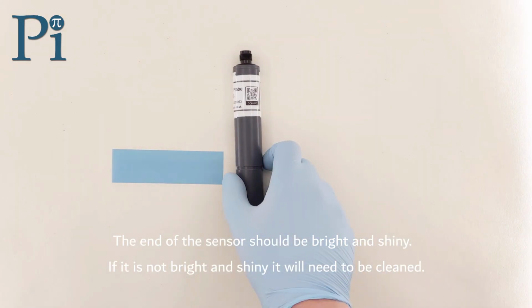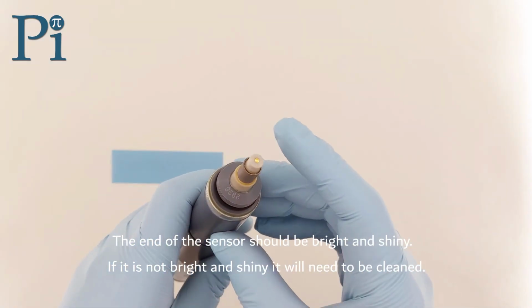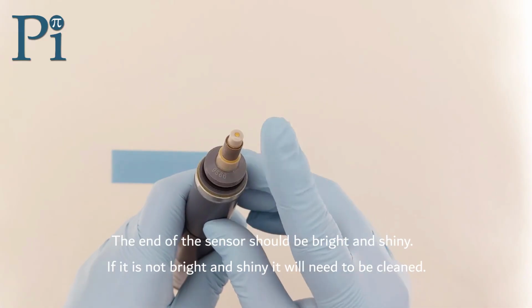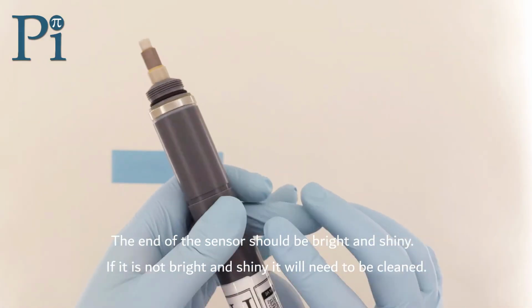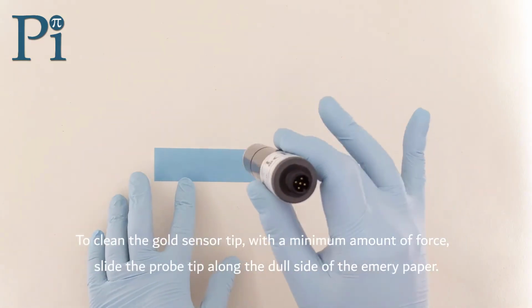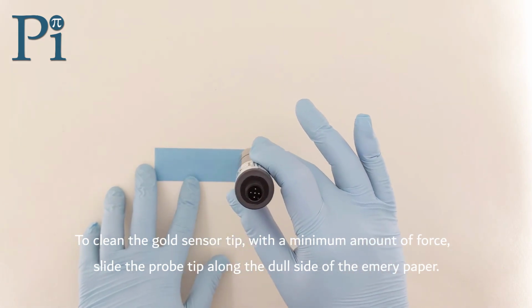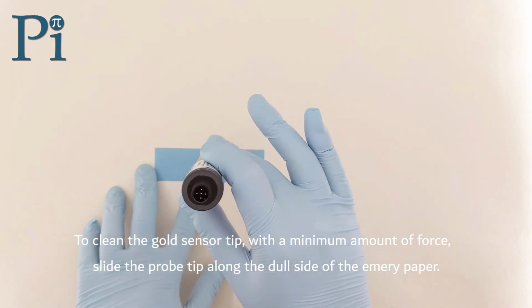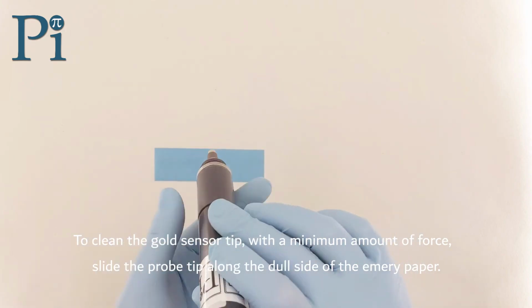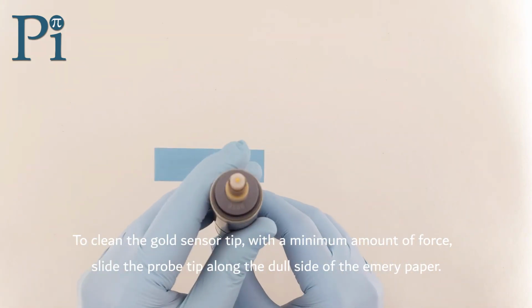The end of the sensor should be bright and shiny. If it is not bright and shiny, it will need to be cleaned. To clean the gold sensor tip with a minimum amount of force, slide the probe tip along the dull side of the emery paper.